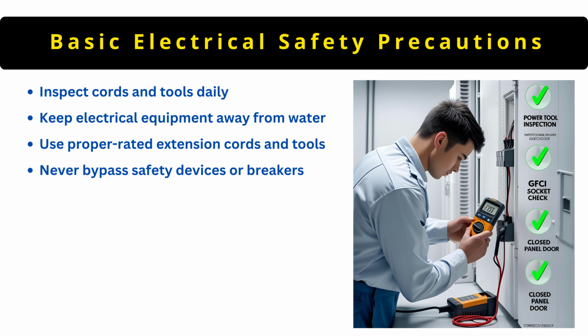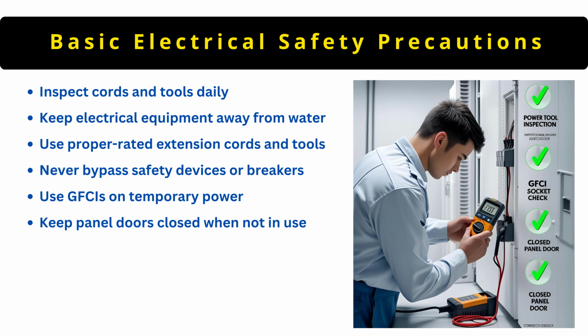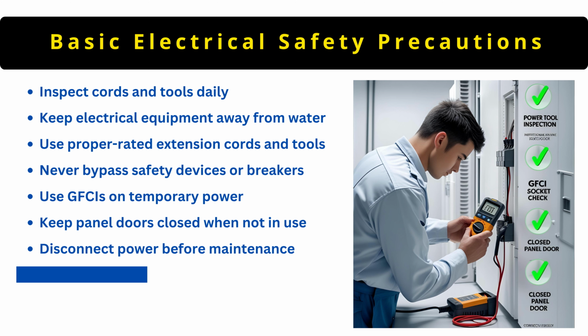Fourth, never bypass breakers or fuses. These are safety devices meant to stop power in dangerous situations. Fifth, install GFCIs for all temporary connections. They quickly shut down power during a fault or current leak. Next, always keep panel doors closed to prevent accidental contact with live parts. Seventh, always disconnect the power before doing any repair or inspection. And finally, ensure proper grounding and bonding. This safely directs stray currents away from your body.